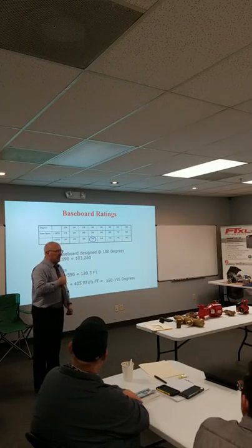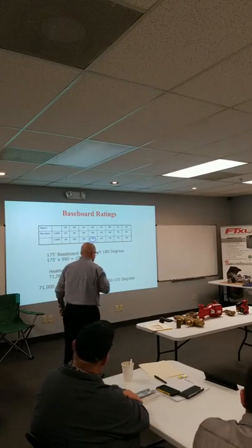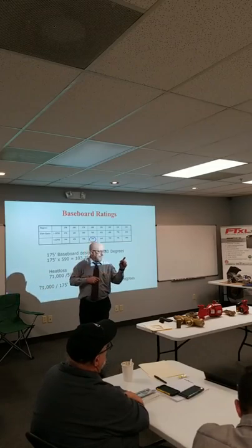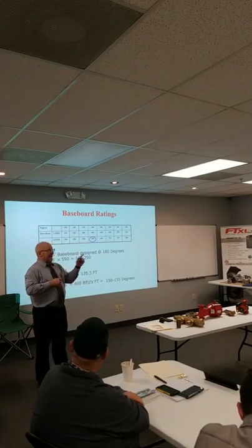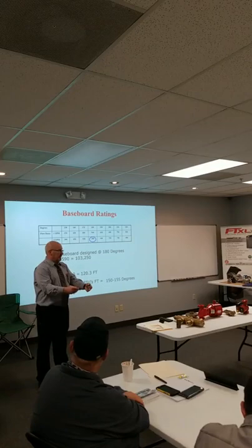am I going to see 95% efficiency? No. What is efficiency? When they say a boiler is 95% efficient, what is it? Does anybody know? For gas-fired appliances, basically efficiency is how much heat you're getting out of it and how much you're throwing up the chimney. AFUE, annual fuel utilization efficiency, is what they rate boilers in. How many BTUs of gas you bought, how many BTUs went in your house?